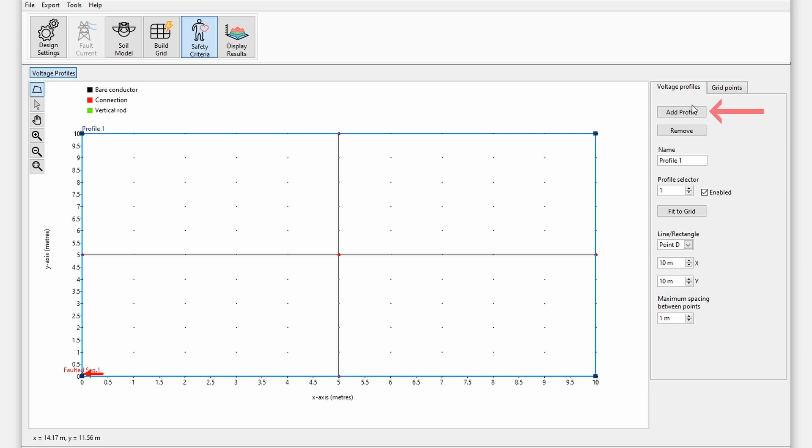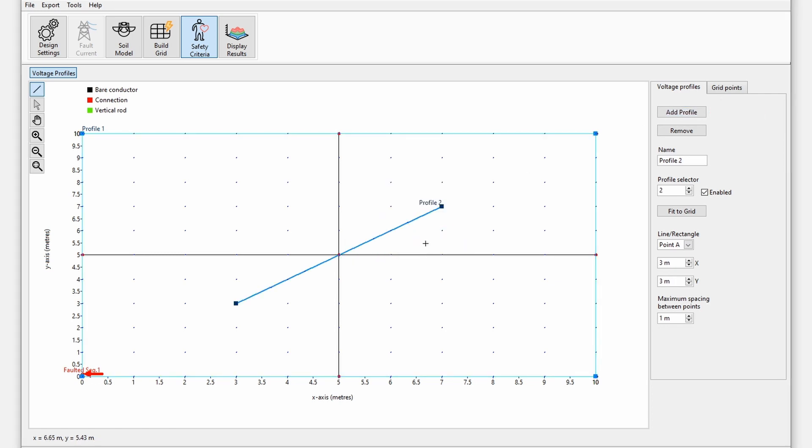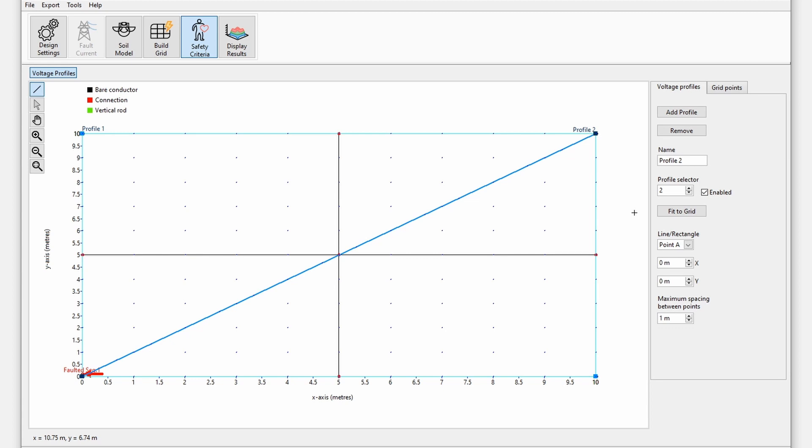Add a line profile by pressing add profile and select line profile. With the line profile selected, press fit to grid. Note for transient calculations it is recommended to use line profiles rather than rectangular profiles to minimize the number of voltage points and hence reduce calculation time.